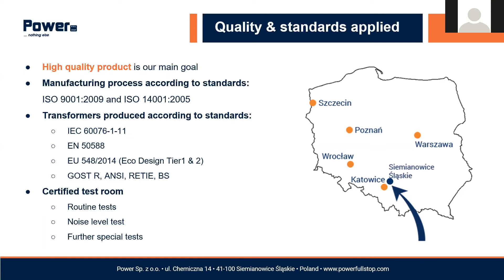Our power range starts from 10 kVA up to 5 MVA. The limit, for now, is a weight of 10 tons. Voltages start from 1.1 up to 36 kV, sometimes even higher for the Russian market. Our standard is to reduce eco losses, and now we are ready for Tier 2 of the new directive.